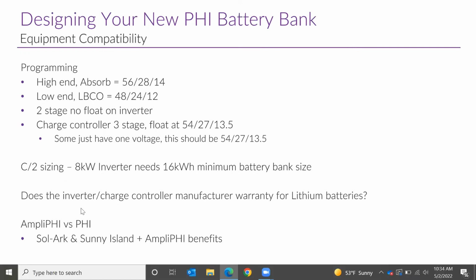One thing to consider is, does your charge controller or inverter manufacturer warranty for the use of that equipment with lithium batteries? And if not, you might consider replacing it with a Sol-Ark or Sunny Island inverter. These are two new, more advanced inverters. If you do need a replacement, they have a high level of pairing and, I'd say, information sharing with our batteries. So you're able to upgrade to the newest model inverter as well as the newest model battery, and those two things can talk to each other. So there's a lot of benefits there, which we go into deeply in other trainings.